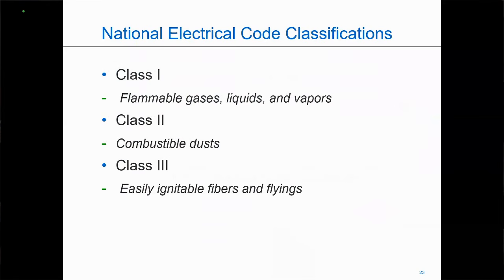But once we know what our classification is, we're going to want to start selecting material. So Class 1 is our area with flammable gases, liquids, and vapors. Class 2 is our area with combustible dust, and Class 3 is easily ignitable fibers and flyings. Sometimes people think these particular classes are ranked in the order of danger. Nothing could be further from the truth. When you have an area with gases and vapors, that's going to be an explosion followed by a fire. Combustible dust can often be multiple explosions followed by the fire.